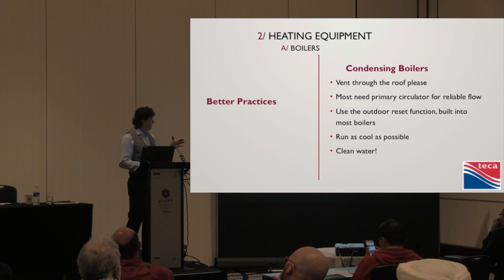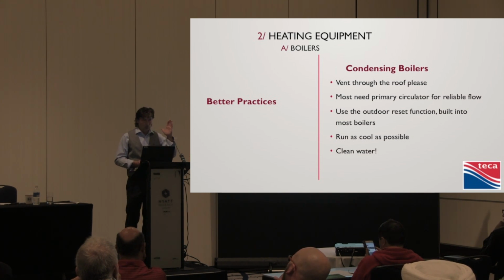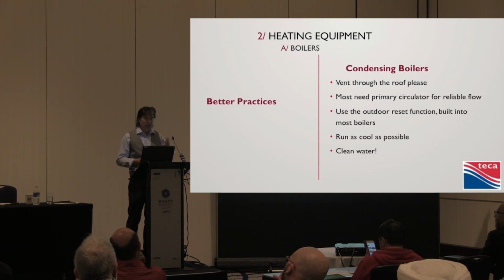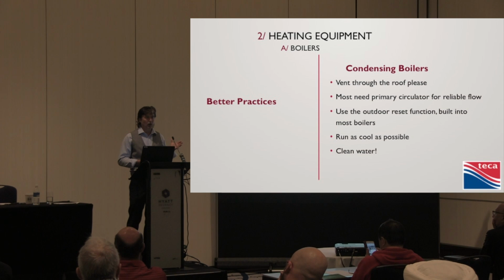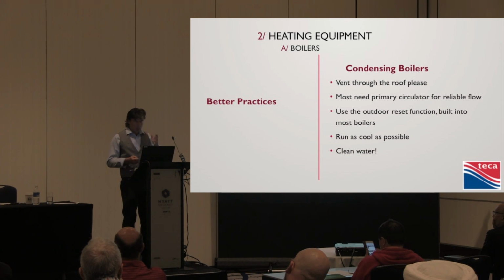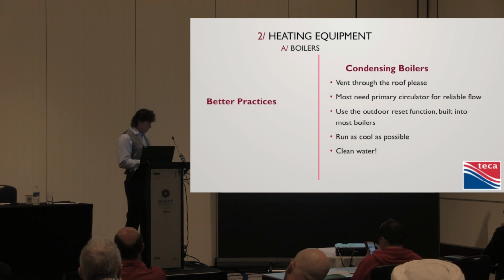But here, let's just go through the roof, especially if it's new construction. Most of them have the venting range to get through the roof. So if somebody's telling you, no, it won't work, I've got to go sidewall. I mean, that sidewall vent is there forever. And it's going to steam up the side of the house, your soffits, your windows. You've got to have the clearance of windows and all. When you think about it, why are we doing that? Why didn't we just go through the roof? Is it really that far to go? Sometimes you've got to upsize the piping or whatever. There's a little extra cost, but for God's sakes, put it through the roof.